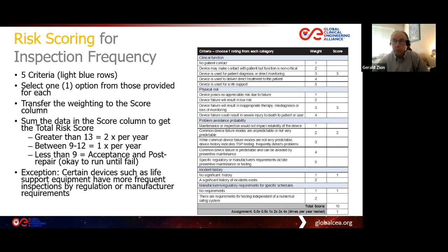All right. This is the worksheet from the textbook that I talked about, used by the University of Vermont Biomed Department. They fill in this worksheet when they do an incoming or acceptance inspection test of a medical device that is not yet in the inventory, or has been sent away for repair and comes back. The important things here are to help us decide how often we should do testing, what the risks involved are, and even if the manufacturer also has a recommended inspection frequency.